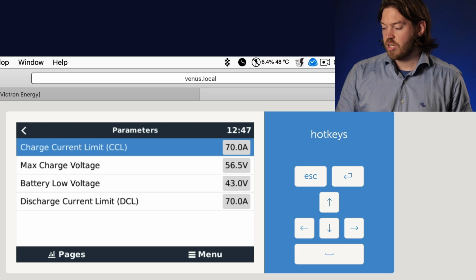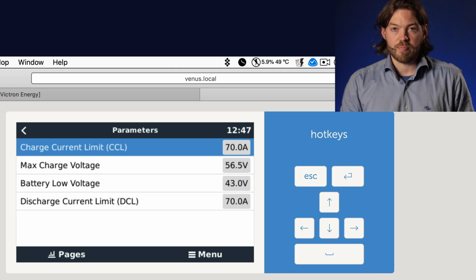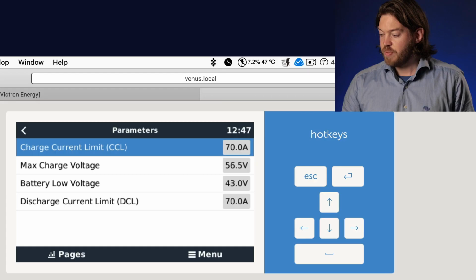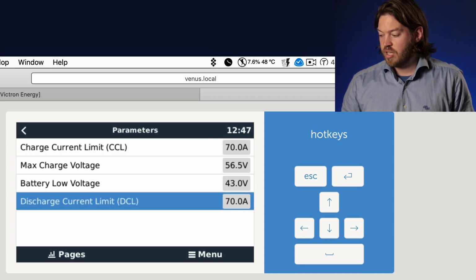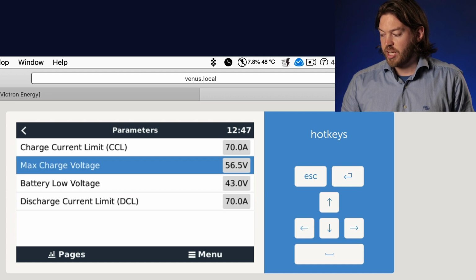Okay, the system's going to stabilize at 70 amps of charge current limit. If this doesn't increase, it's because there's some issue with the system — it could be the batteries are just too cold, or it could be the batteries are 100% full, in which case they don't want any more charge current, and they'll say the charge current limit is 0. Now these batteries are looking like they're behaving properly — I'm seeing 70 amps charge current limit, 70 amp discharge current, and a max charge voltage of 56.5.